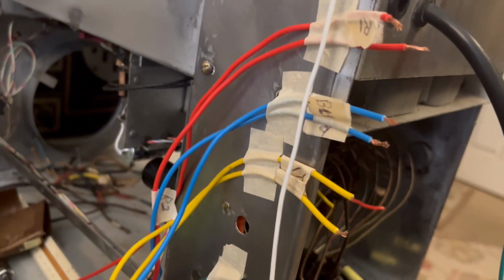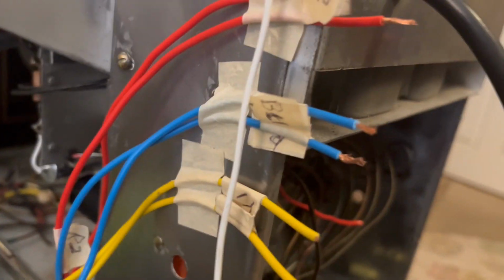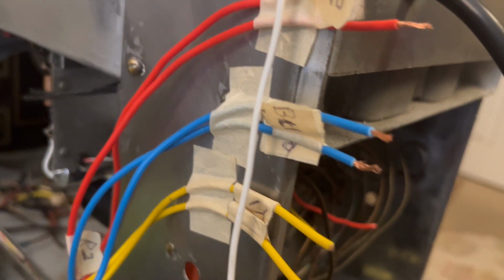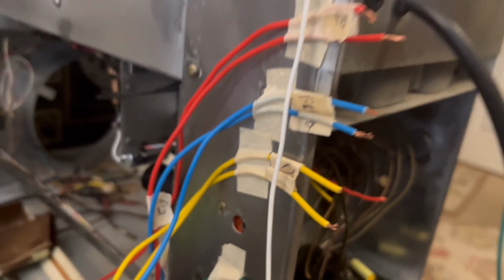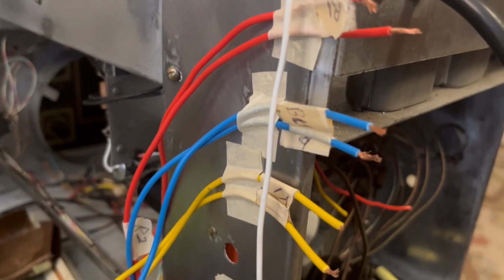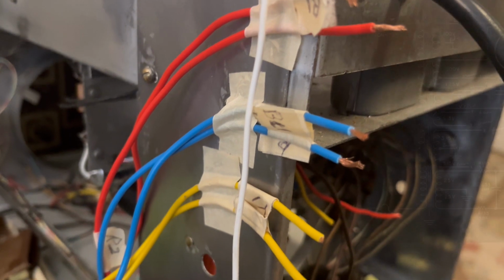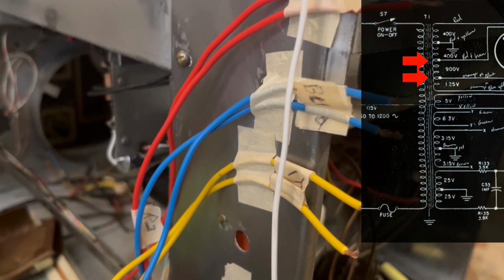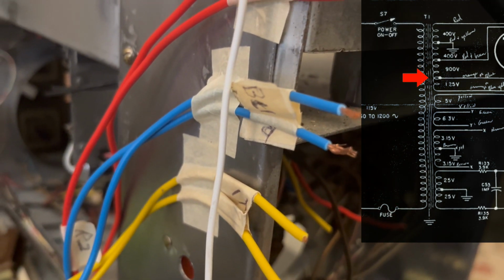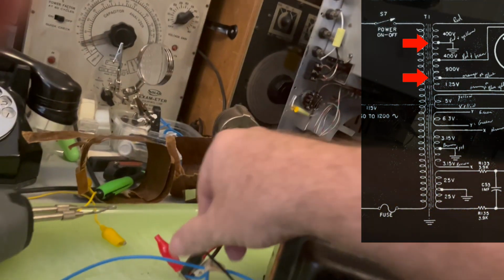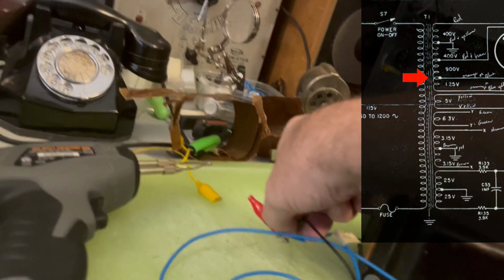The next thing to do is to check each one of these coils separately. I can't measure this high voltage one, the blue one that you see there. That's the one that I had to wrap 2700 on. I can't really measure that from there because my meter will burn out if I try to. It'll be at least 900 volts if I was to read it from that lead, and it would be 1300 volts if I tried to read it from ground over here. So really all I can do is measure the potential across that coil.